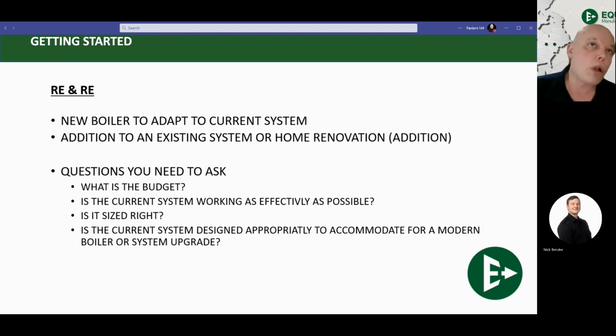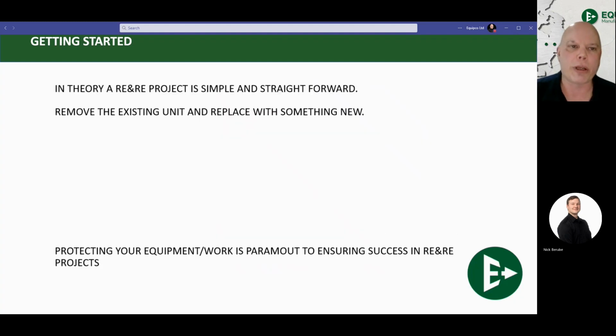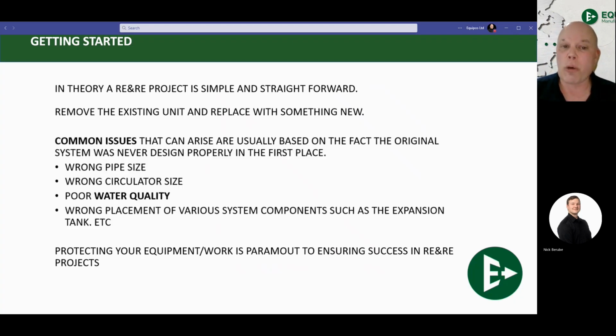So if you're taking out a really old system and putting in a brand new one, you're probably going to be looking at more than just a boiler replacement. Probably going to be the addition of some pumps and some trim and stuff like that. So that's a common question that we want to make sure gets addressed before we do anything too deep in the re-and-re. Re-and-re should be very straightforward and simple. We're just removing the existing, replacing with something new, but it doesn't always work like that.